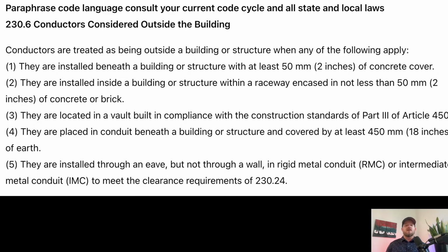So there are several ways conductors are considered outside of a building: 2 inches of concrete, 18 inches below the earth. This is important because, outside the scope of today, there are a ton of different codes that kick in depending on whether you are inside or outside of the building. Knowing these codes can save you dramatically - can save you distances of running conduit around a building, can save you material when you're dealing with wire.